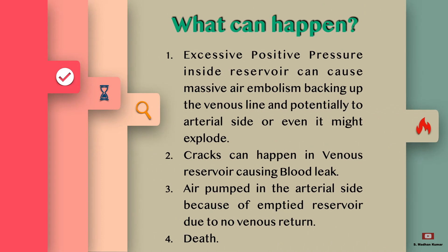Hi all, today we will see over-pressurization of the venous reservoir in the CPB troubleshooting series. What can happen when more pressurization happens in the venous reservoir: excessive positive pressure inside the reservoir can cause massive air embolism, backing way up to the venous line, the cannula, or into the right atrium, and potentially to the arterial side also.